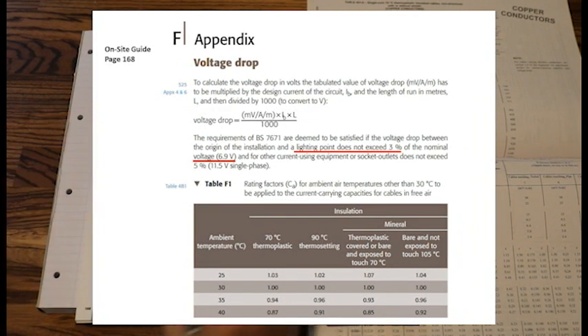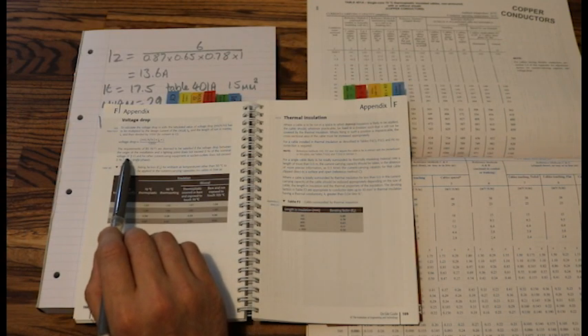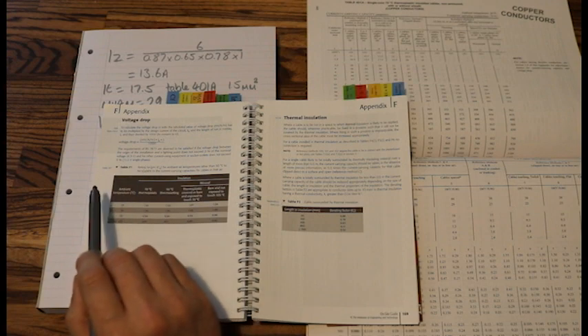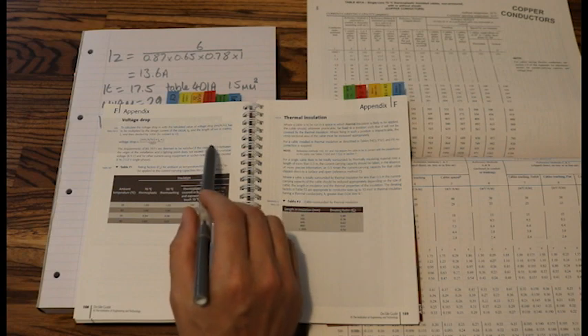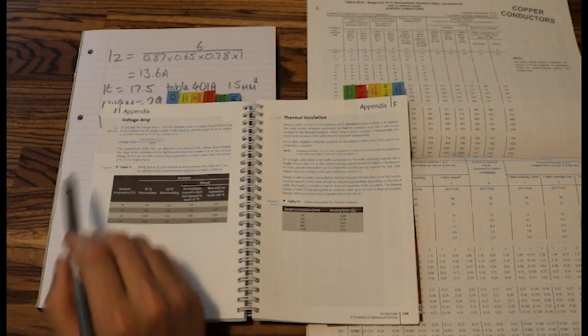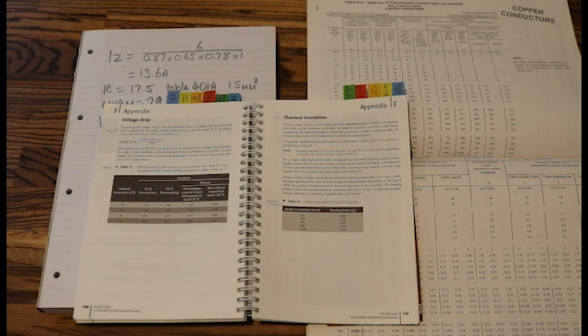Our question is lighting. It says it cannot exceed 3% of the nominal voltage, and then it's got 6.9 volts in brackets. What the onsite guide is doing, it is saving you from calculating 3% of 230 volts, because that is our usual voltage. So 3% of 230 volts is 6.9 volts. So my Voltdrop that I'm about to work out cannot be more than 6.9 volts.